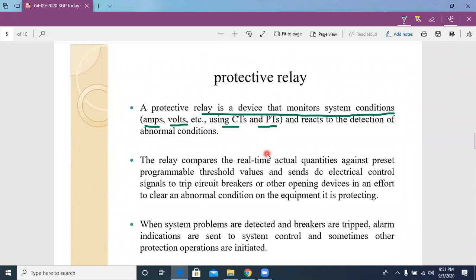So the basic thing about a relay is it continuously monitors the system conditions with the help of the current transformer and potential transformer, and it reacts to the detection of abnormal conditions. It continuously monitors the system condition, and it will also react when abnormal conditions happen in the system. This is the basic function of a relay.